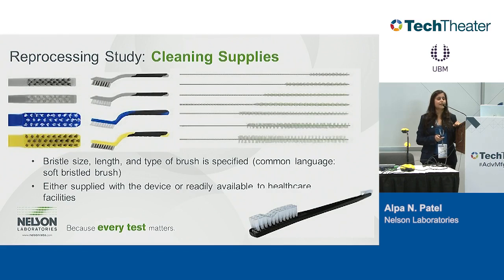Any cleaning supplies that have been used for the validation, usually the FDA will ask what kind of brush was used for the cleaning. If you use any pipe cleaners, what size did you use for those? They are specific, and they do ask for specific reasons, because a lot of times when you're cleaning a lumen, if it's not a tight fit, you're not cleaning anything. So the FDA wants to make sure that during the validation you use the right instrument, and also that in your IFU, when you write it, the right brush size has been expressed in there.